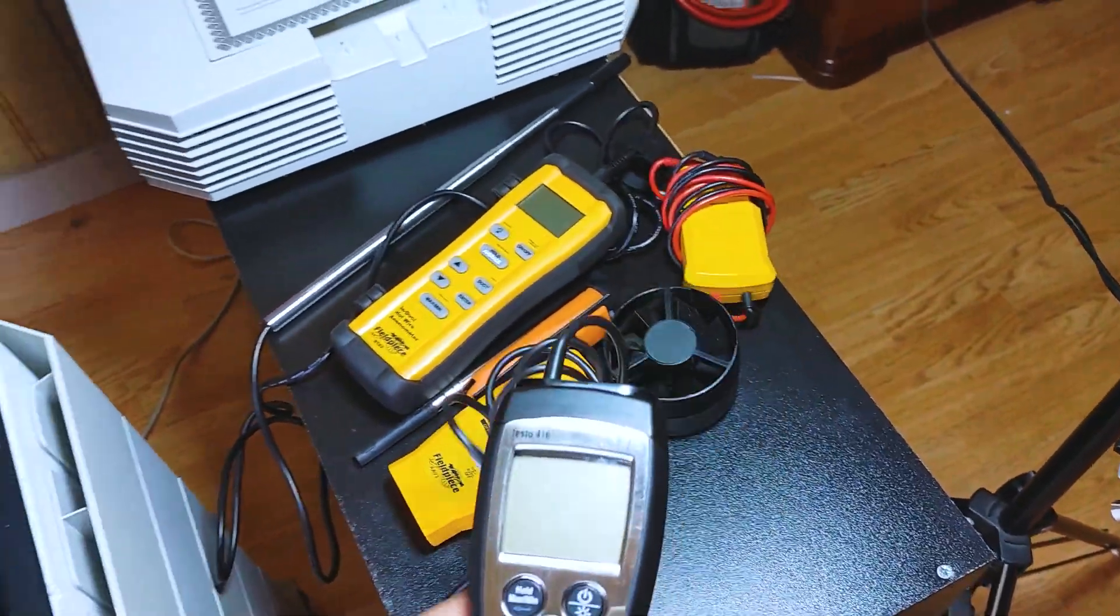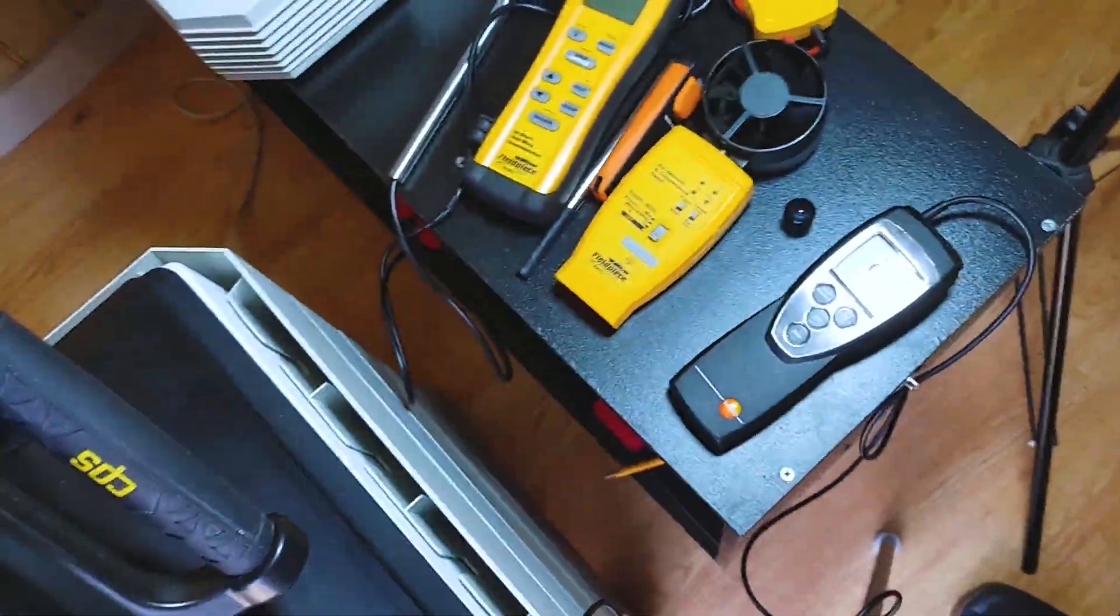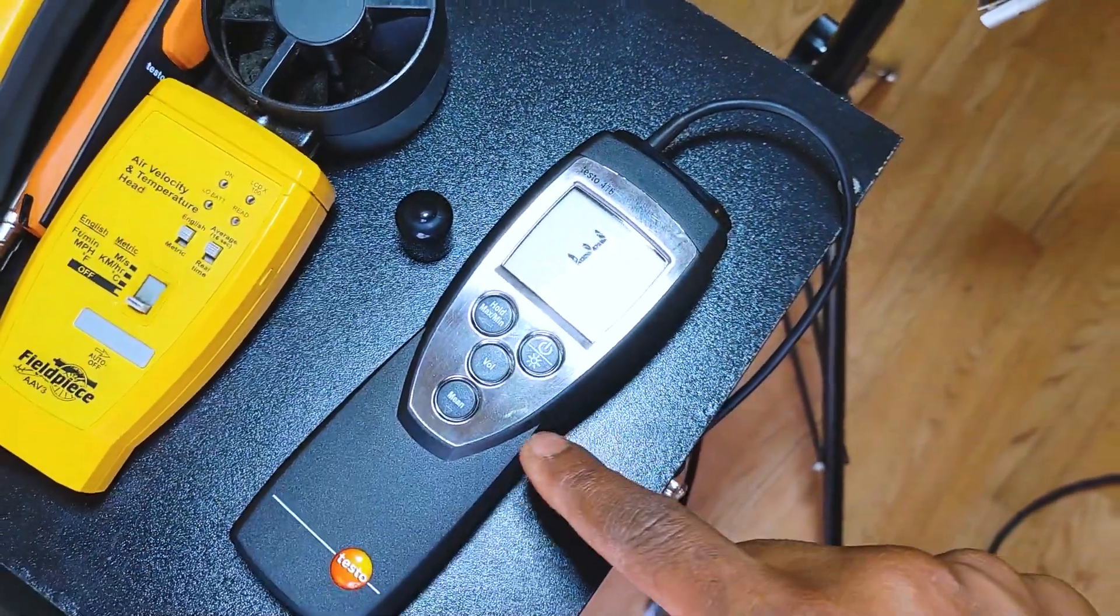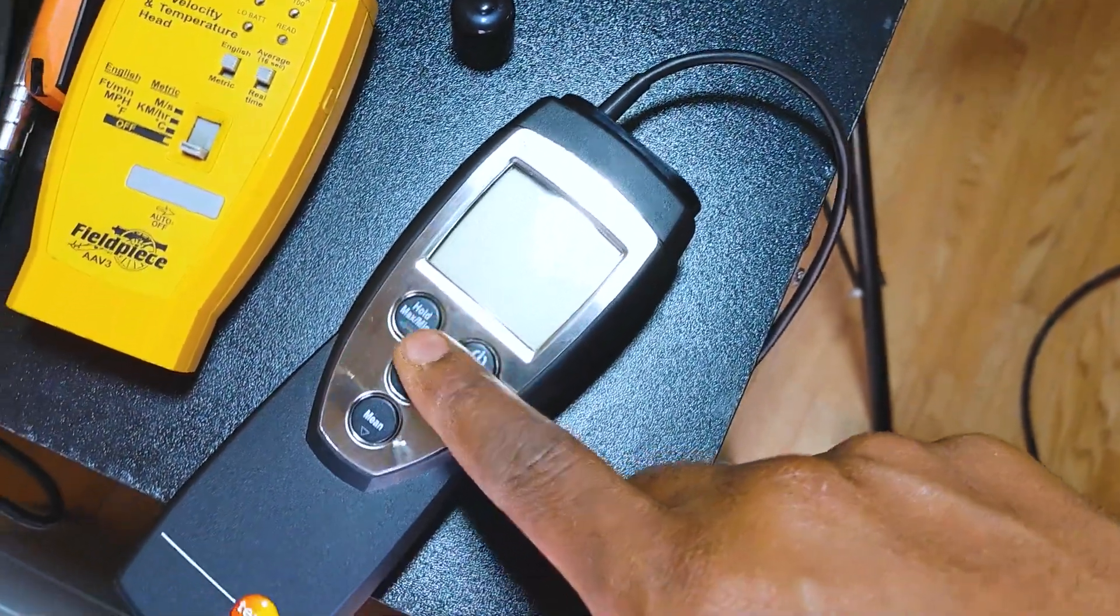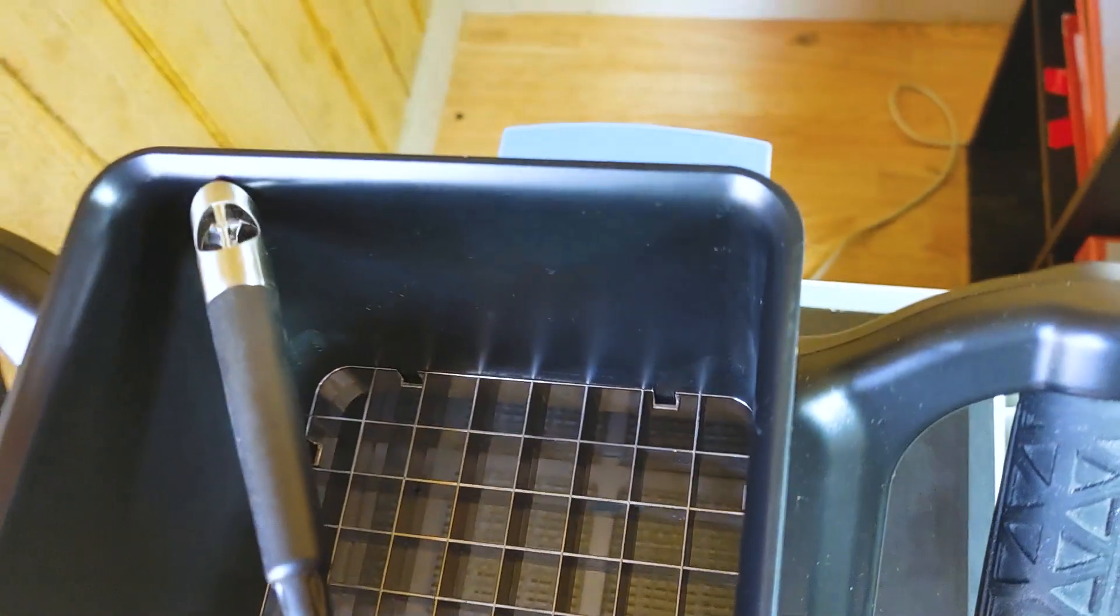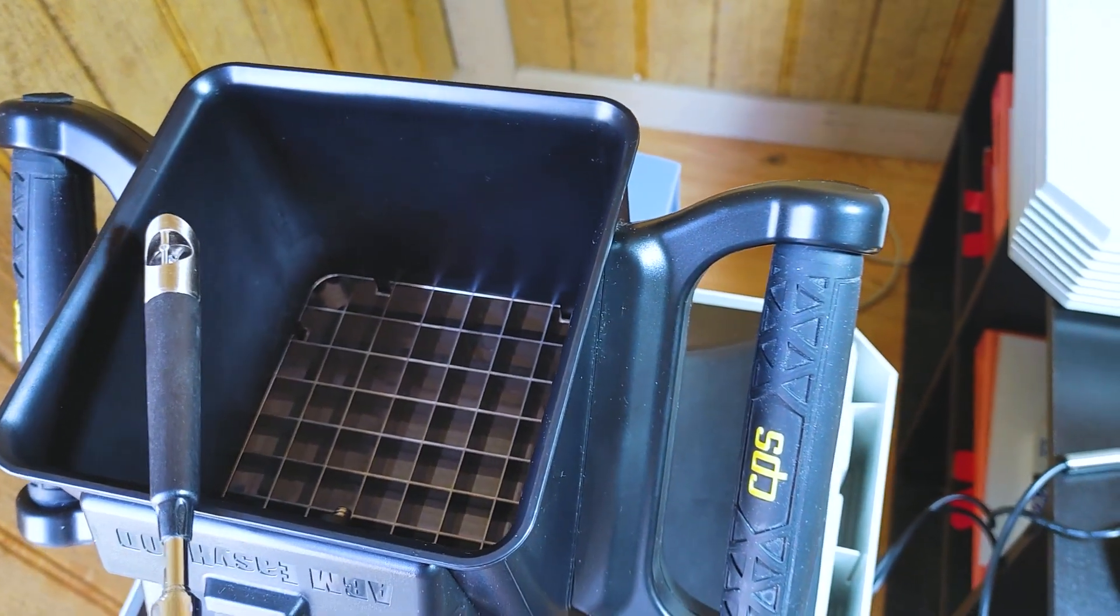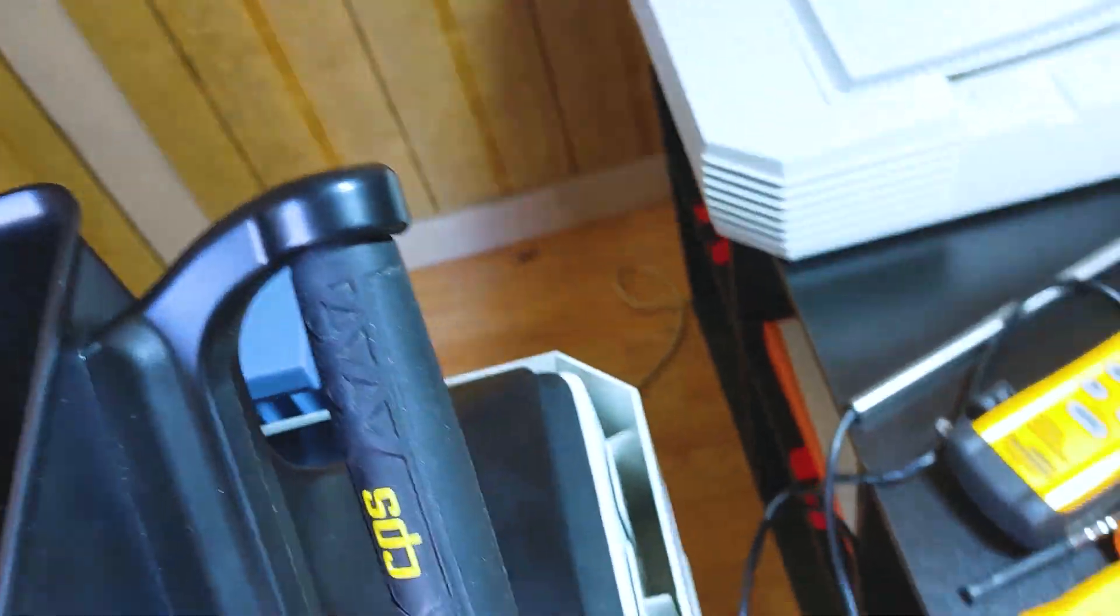Let's go ahead and get this Testo 416 up and active. Now I've got the probe dead center here. Speed one, we're reading 52 CFM dead center. Let's get our traverse, gonna want to hold this here, 36 square inches, that's perfect. We're showing 51 CFM.